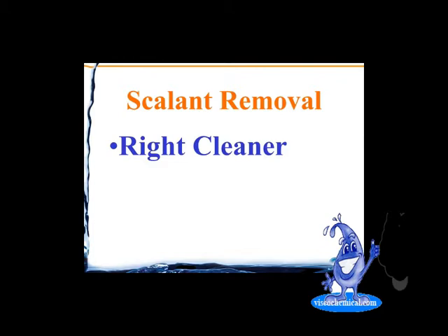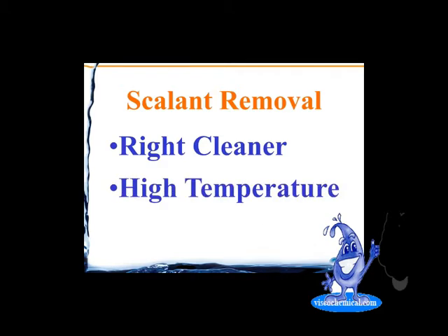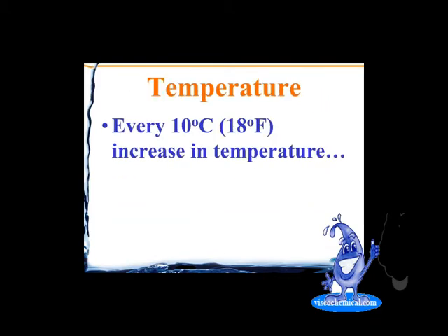So in general terms, we just have to get the right cleaner. We have to clean at an early enough stage to where we can make sure that we can get the cleaning solution to go in, and then the right cleaner, and then a high temperature, and then it's just going to take time. How long is it going to take to dissolve all of this scalant off of the membrane?